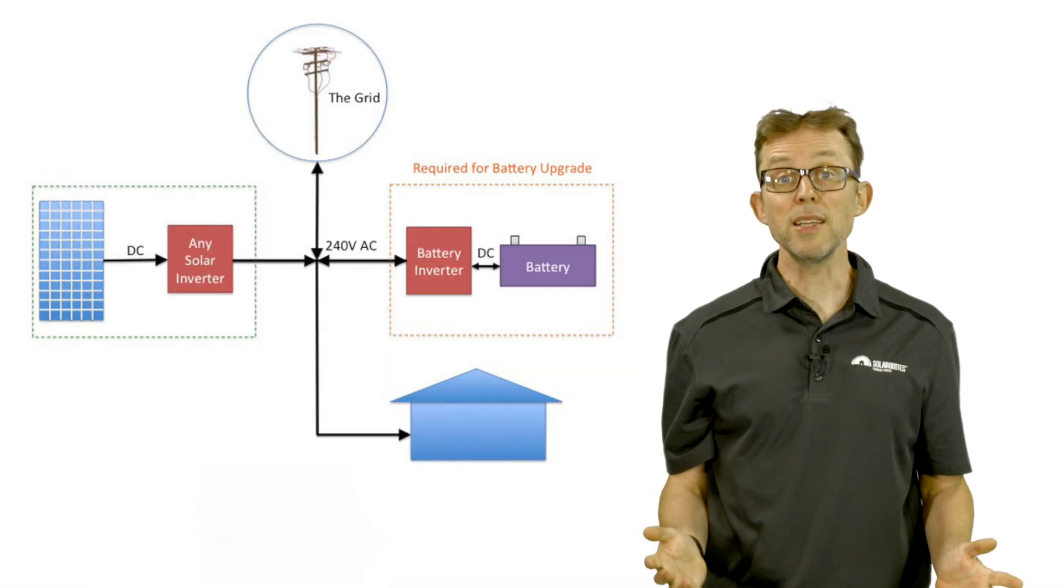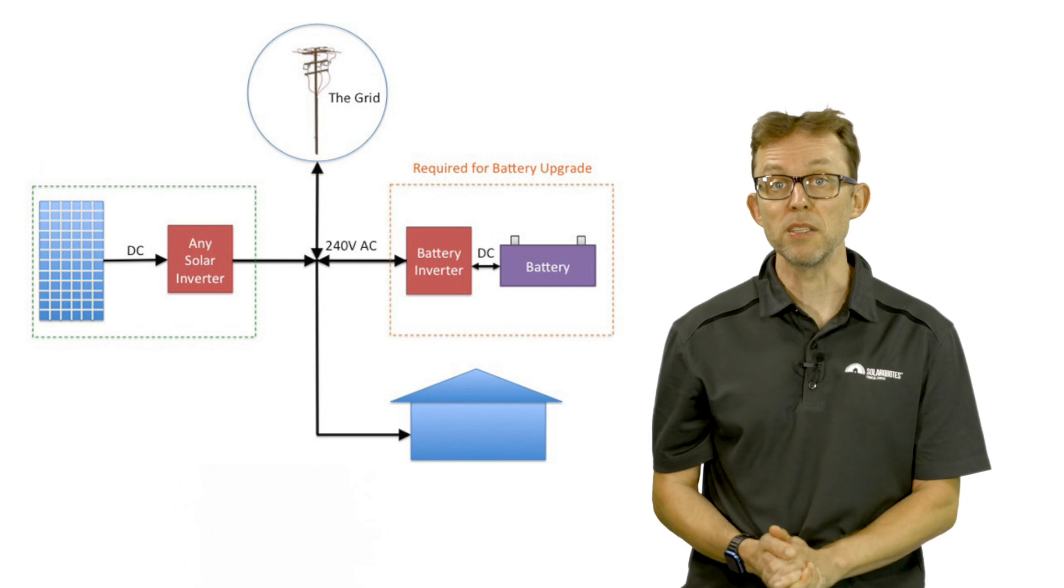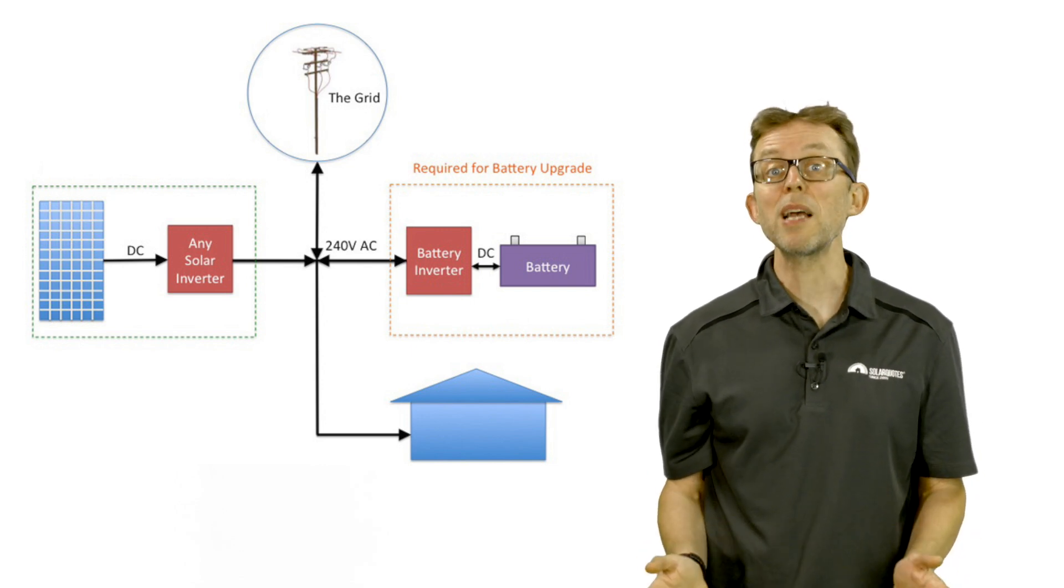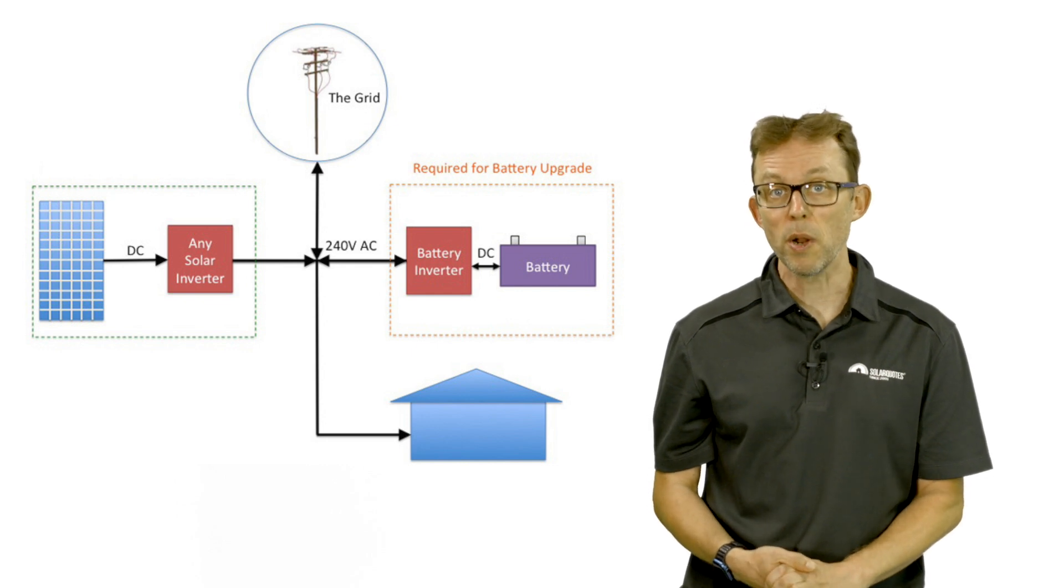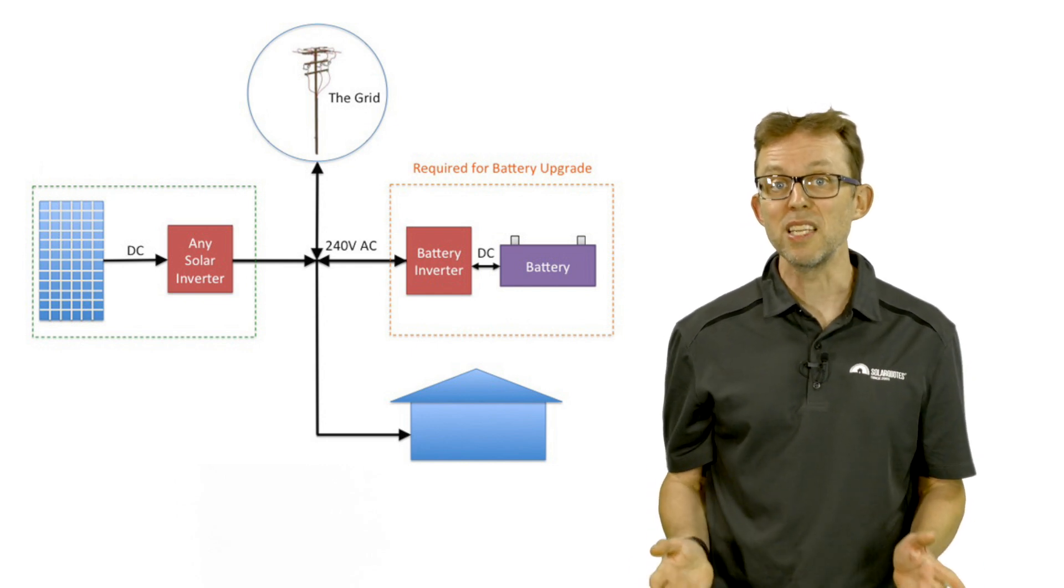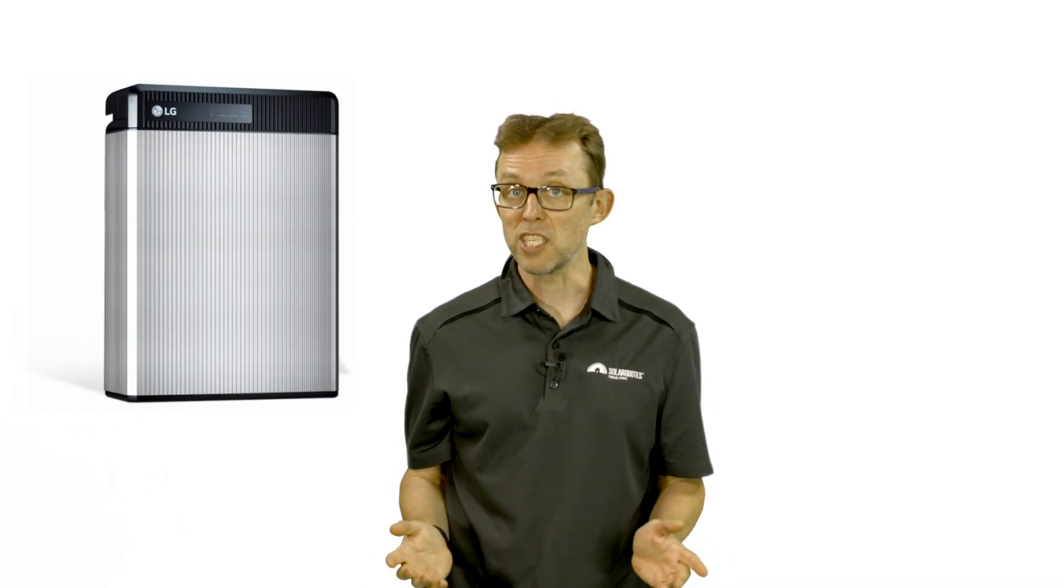The other way to integrate a battery is through AC coupling. With AC coupling, you need two inverters. A solar inverter and a special battery inverter, which converts the AC output of the solar inverter back into DC to charge the battery. Some battery options, such as the Tesla Powerwall, come with a battery inverter built in. The Powerwall can only be AC coupled. Others, like the LG Chem, need an external battery inverter to be installed on the wall next to them.